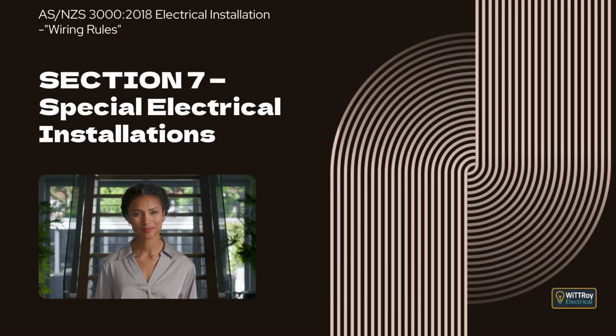Clause 7.2.2.3 Alternative Supply Systems. This clause explains that alternative supplies may be needed so a building can continue to be used safely when the normal power supply is lost. It explains that the alternative supply must have enough capacity to operate all required safety services and, where needed, to support continued occupation of parts of the building. It also explains that generating sets or other independent power sources must be sized to supply all safety services at the same time, including allowance for motor starting. The clause notes that a separate alternative supply may also be provided for non-safety purposes such as security or protecting business assets.